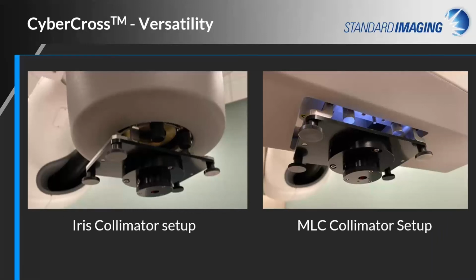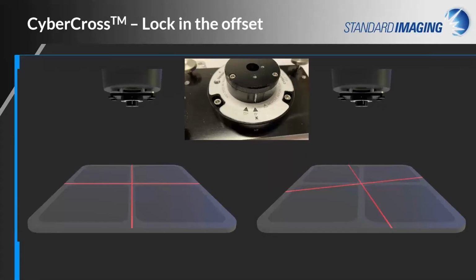The CyberCross device can be installed on fixed, iris, and InCise MLC collimator housings. CyberCross attaches to the CyberKnife system's proximal coupler and is held in place by set screws. CyberKnife commissioning and annual QA require the acquisition of scans at a 15-degree offset. Once again, a laser point is insufficient for easy realignment of a 3D water scanning system. This task is made fast and easy with the CyberCross installed and locked in the offset position.